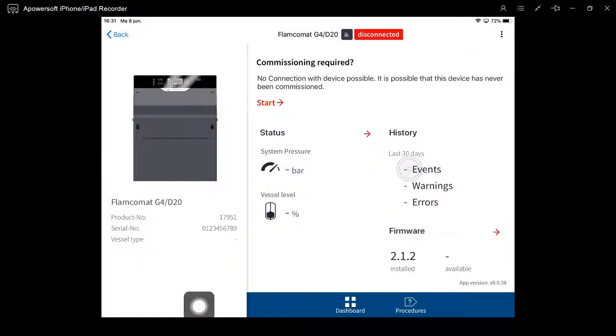Here we have the Flamcomat G4. It's not powered yet, and by scanning the QR code, the device will detect that this is a Flamcomat G4 D20 with the product article number 17951. We can also see that we can't read the pressure and vessel level yet. There's no history and no firmware, and it says commissioning required.